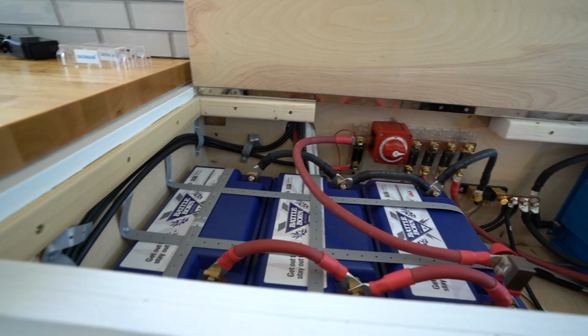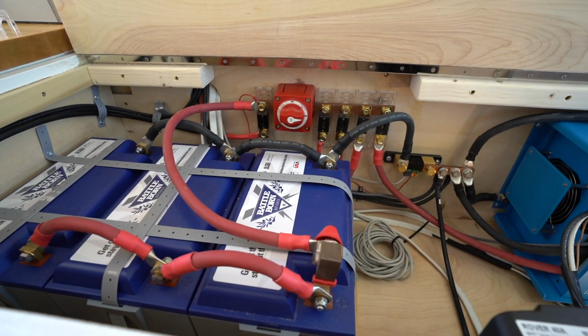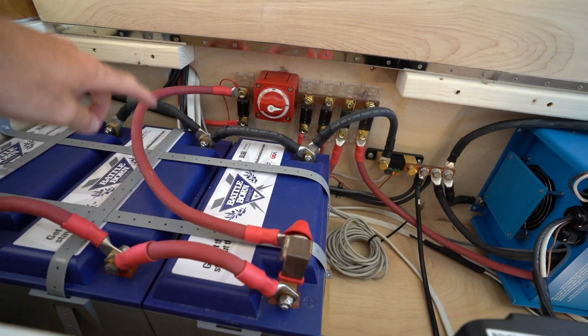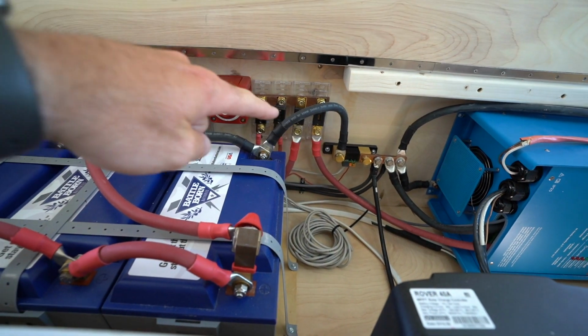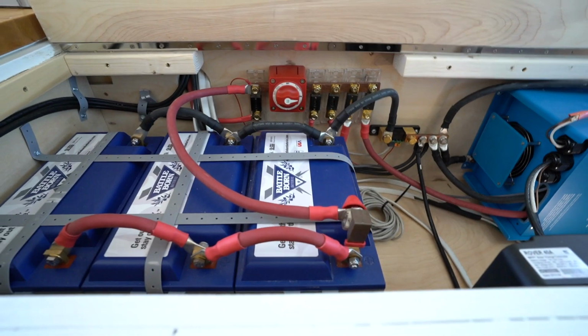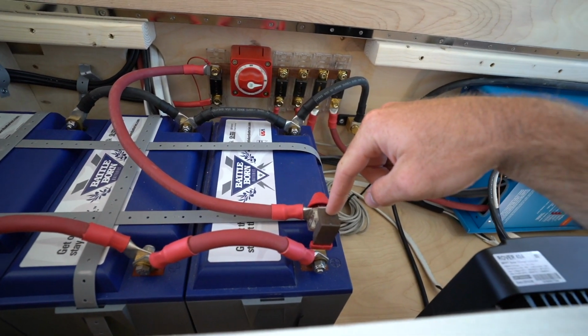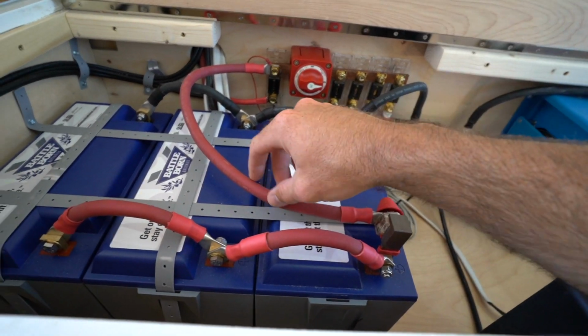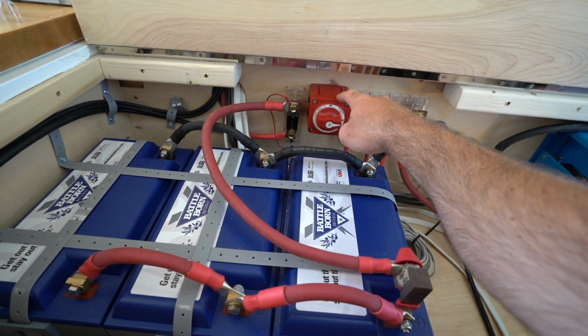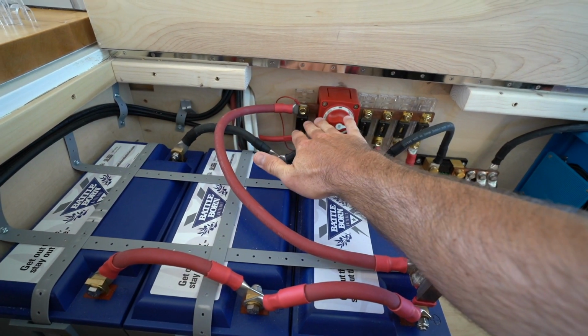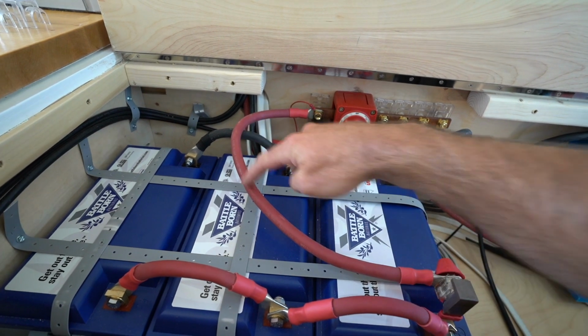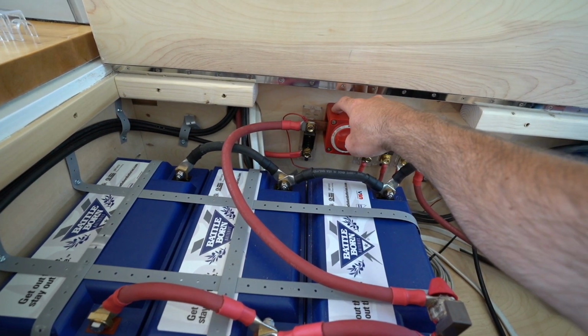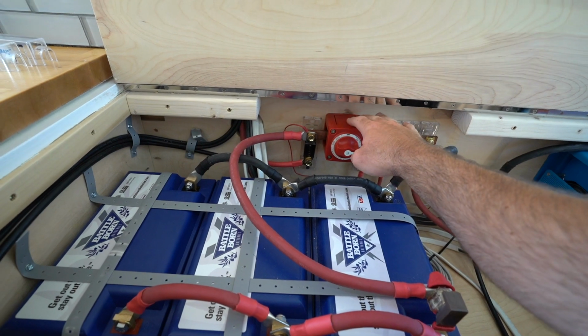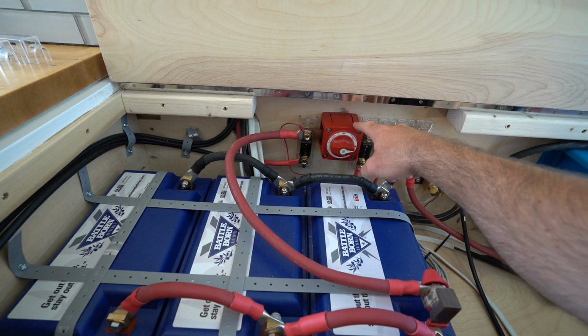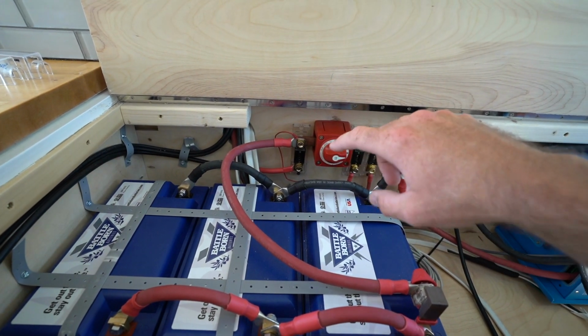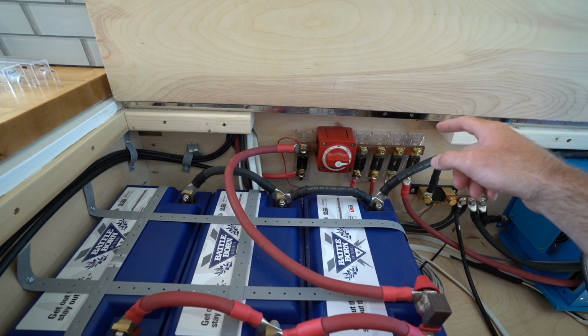The real brains of the operation run from our batteries to the bus bars, both positive and negative. For the positive, we have a 300 amp terminal fuse connected to a 2/0 wire that goes to our master kill switch. On the left side of the switch is the battery wire coming in, connected to a copper bar. I'll put in a couple clips describing how we built the bus bars; if you don't want to watch this, jump to the next clip.